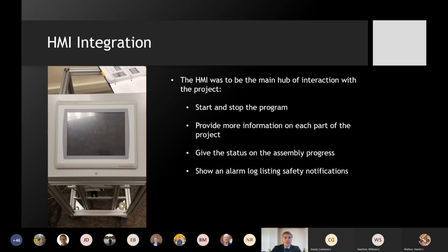Onto the HMI, which we can see mounted on the cart. HMI stands for Human Machine Interface, functioning as an interactive touchscreen for inputting commands into the PLC and displaying program information. For our application, the HMI was to start and stop the assembly program, provide informational screens on how each part of the project operates, give a visual status update on assembly progress, and show an alarm log listing safety notifications, such as an e-stop press or a door opened during motion. Unfortunately, due to COVID-19, many features were not implemented before our time concluded at the college.